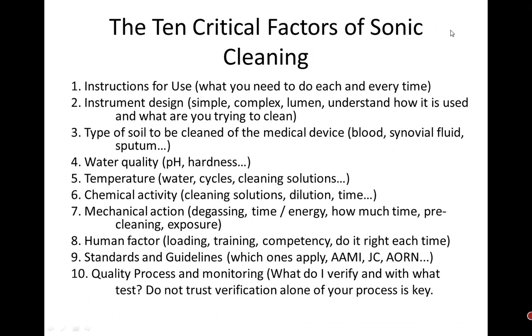And then on top of it, the right dosage. Too many times I will go in and look underneath and see that it is dry, or there's water in the line, there is air in the feeding line into the sonic. And somebody says, well, it's supposed to be blue, or it's got a little bubbles. So again, that cleaning activity, if you're not getting the right dilution, and how do you check and do that?